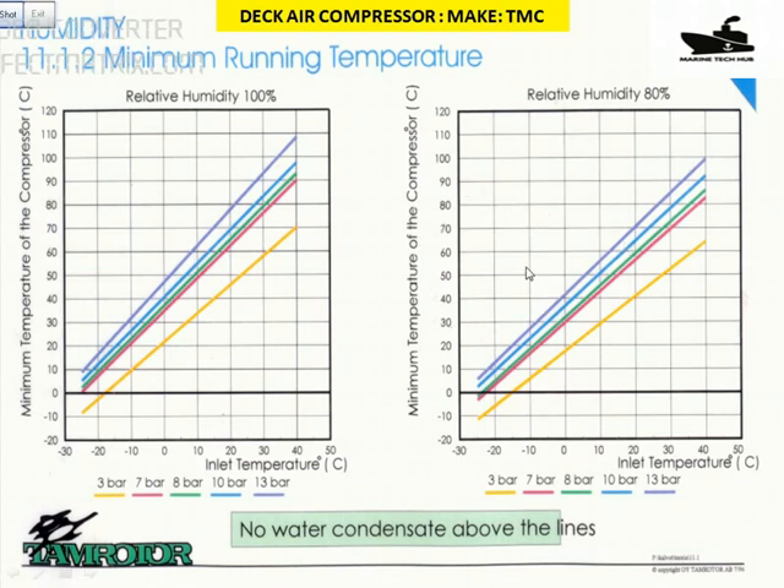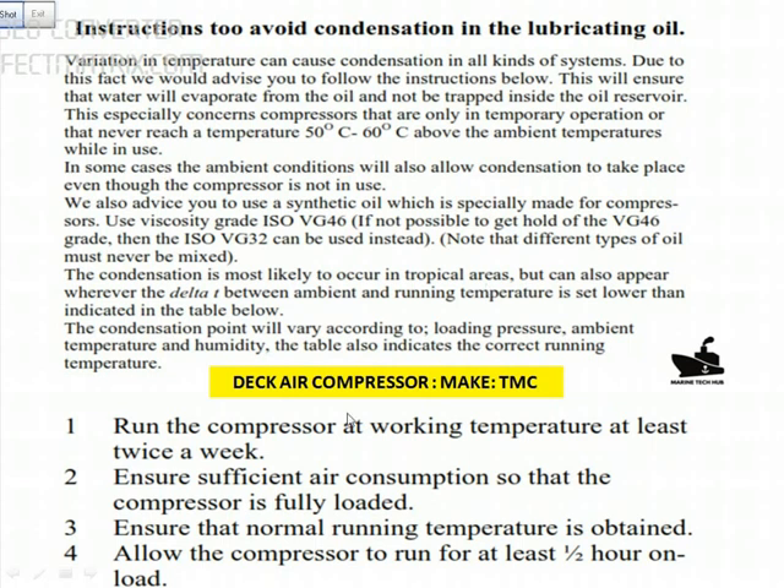The important thing to note is you need to run the compressor at least twice a week if you are not using the TMC compressor. Run it at full load for at least half an hour. When you run like this, there is always a possibility that water condensation will not take place. If you are not running it, condensation can take place and you will spend a lot of money on maintenance of the deck air compressor. Please remember this for safe running and to save money and time for the company.